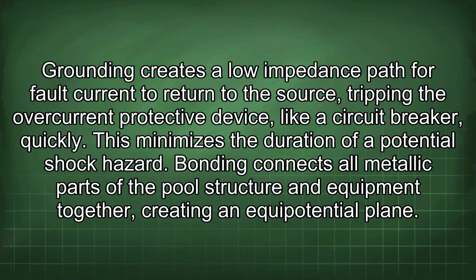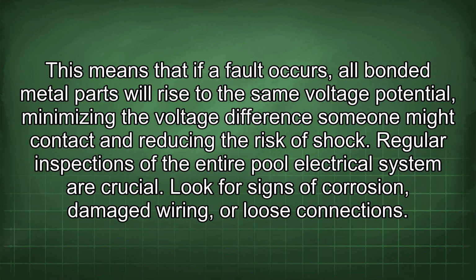Bonding connects all metallic parts of the pool structure and equipment together, creating an equipotential plane. This means that if a fault occurs, all bonded metal parts will rise to the same voltage potential, minimizing the voltage difference someone might contact and reducing the risk of shock.